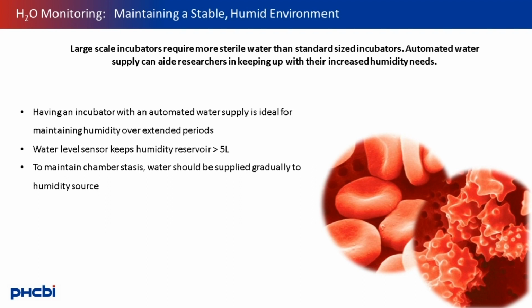Increased incubator capacity creates an increase in humidity demand. A large capacity incubator should be designed to maintain water levels above 5 liters at all times. It may be beneficial to consider an optional additional water supply to aid in humidity demand. Over longer periods away from the lab, an additional water supply can help ensure that the humidity source doesn't dry out. It's also important to make sure that the water is supplied gradually to the humidity source to avoid variations in temperatures. Other conditions, like a very dry climate or dry ambient conditions, can create a need for increased humidity as well.